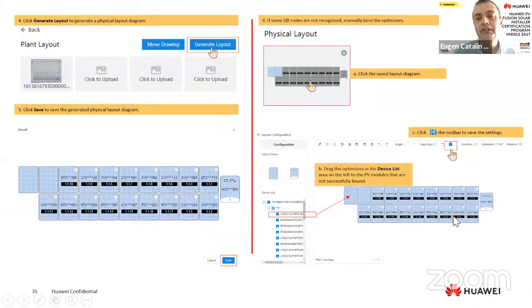Why do I need to create this layout? Imagine the strings are on the roof, one of the panels or optimizers is faulty, and I need to go exactly there. If I don't have the layout, I will only know that on string one I have a faulty optimizer or panel, but I don't know the position. So I need to check all the panels of that string. It is not good to check one by one to search for the faulty serial number. So creating the physical layout is recommended.